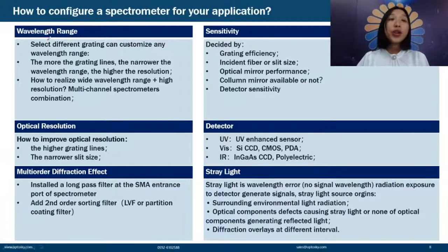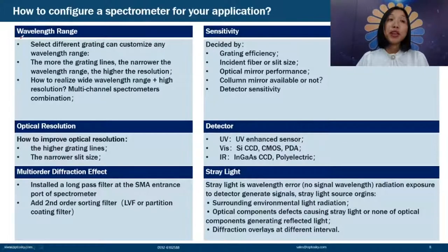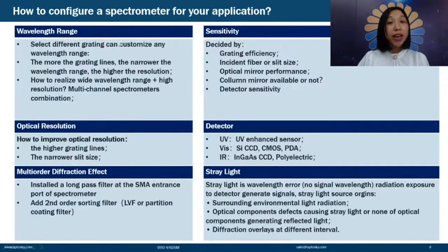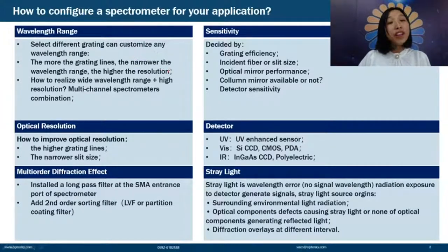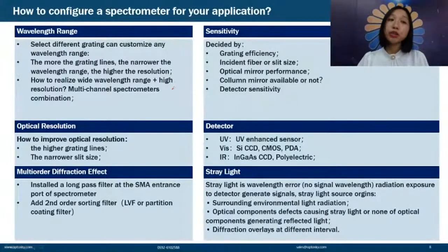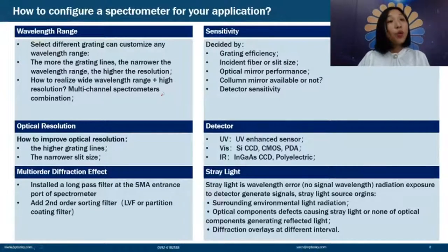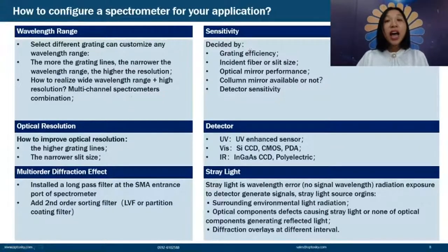Next, we introduce how product managers configure spectrometers for your application. First, consider the wavelength range. By selecting different gratings, we can customize any wavelength range. The more grating lines, the narrower the wavelength range, but the higher the resolution. To achieve both a wider wavelength range and higher resolution simultaneously, we can combine multi-channel spectrometers.